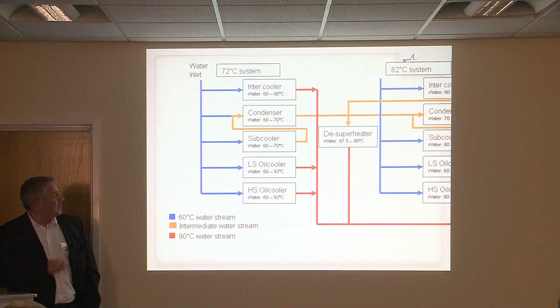And that's the town in Norway. A new district heating plant is in there, taking water out of the fjord, with a reasonably complicated circuit on the water side. The purpose of mentioning the three different phases is that when we look at it all together, we've got three heat pumps operating in series, with lots of areas where we're gathering heat - even taking heat from the water-cooled motors and putting it back into the system, worth about 1% in energy performance. So really trying to gather heat in every single area of the plant.